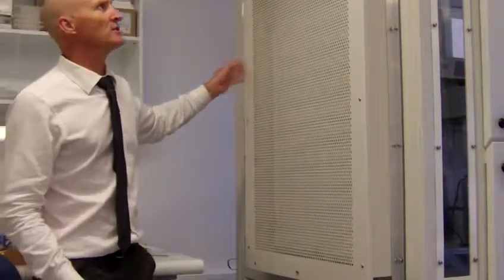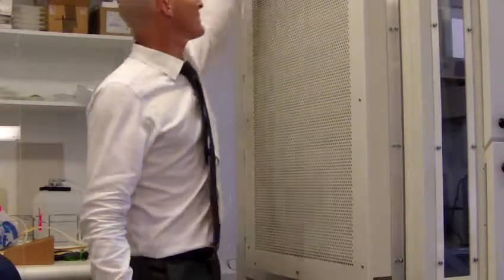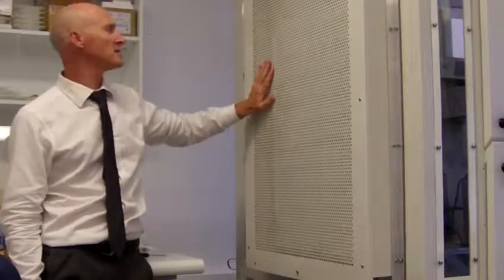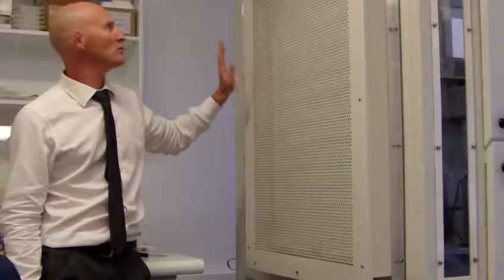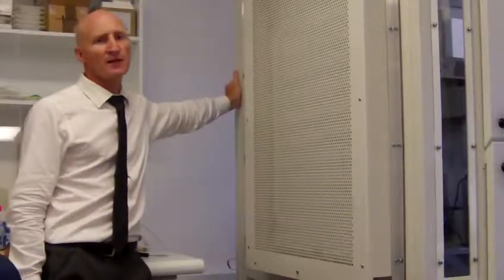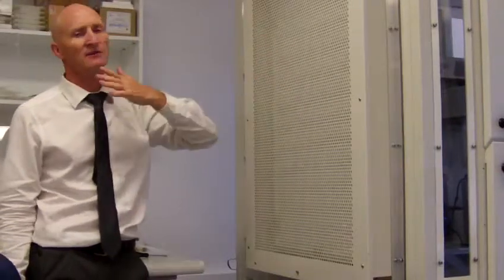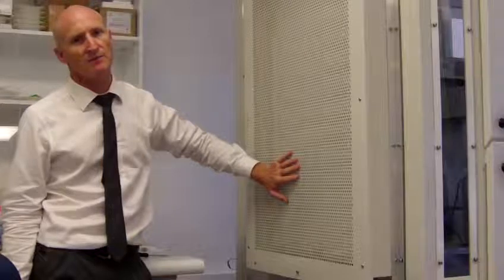The first thing you need to do is remove the plastic cover from the BiGNi. We did it at this end. This filter could potentially be mounted at any point on the unit, so you could mount it on the back if you had clearance. Make sure you've got enough clearance so that there's enough airflow to come out. You don't want this pushed up against the wall because that won't work.